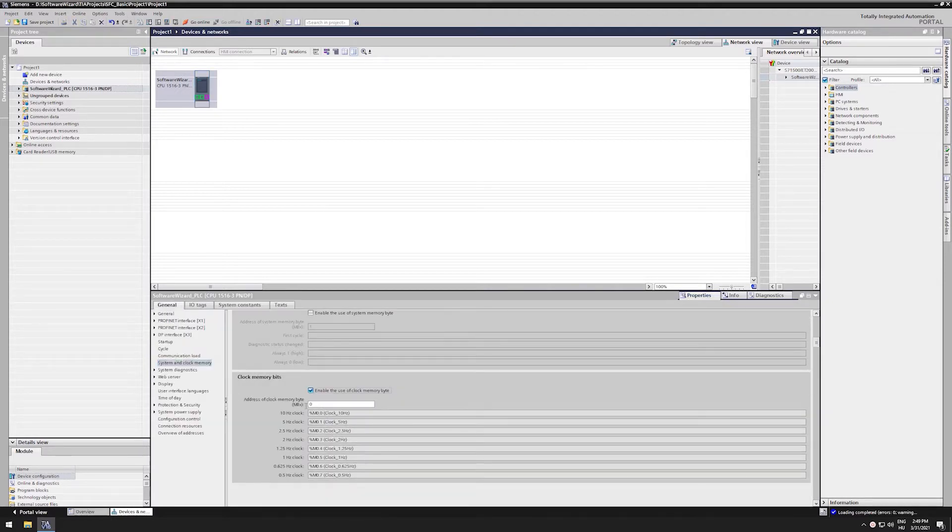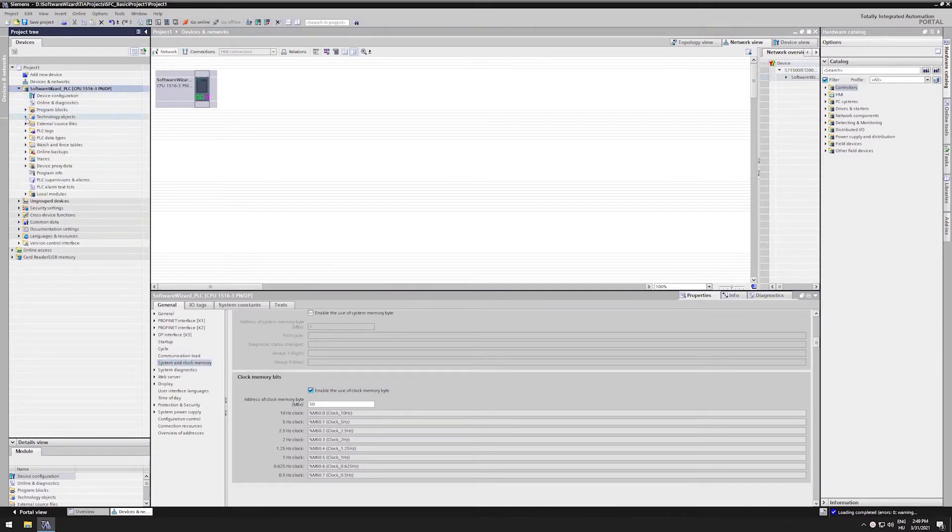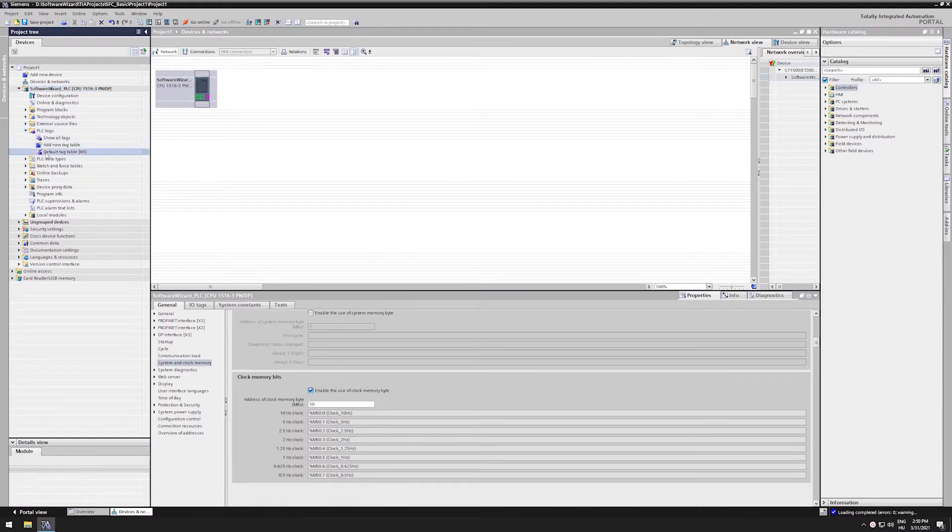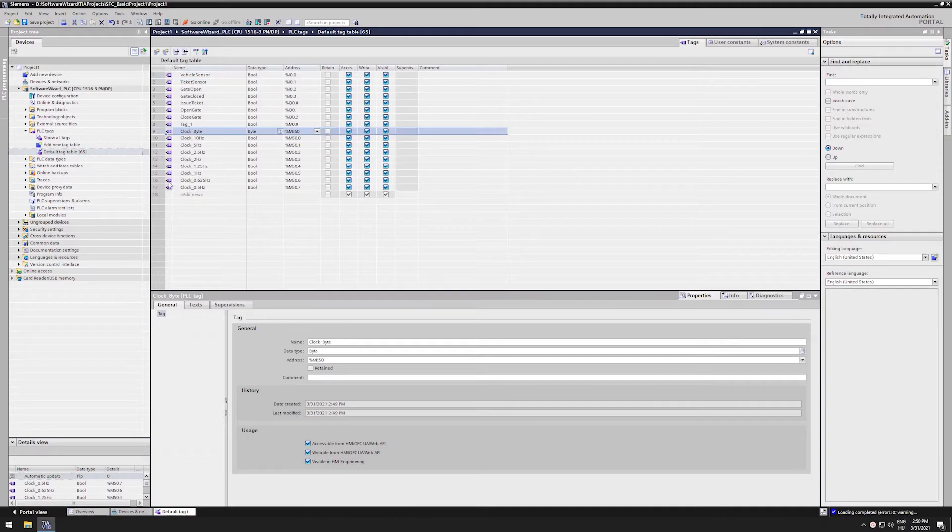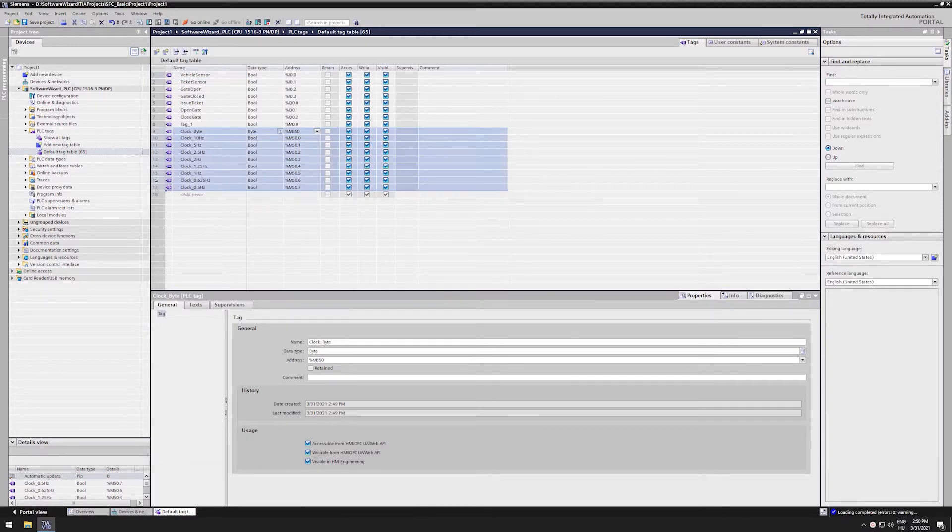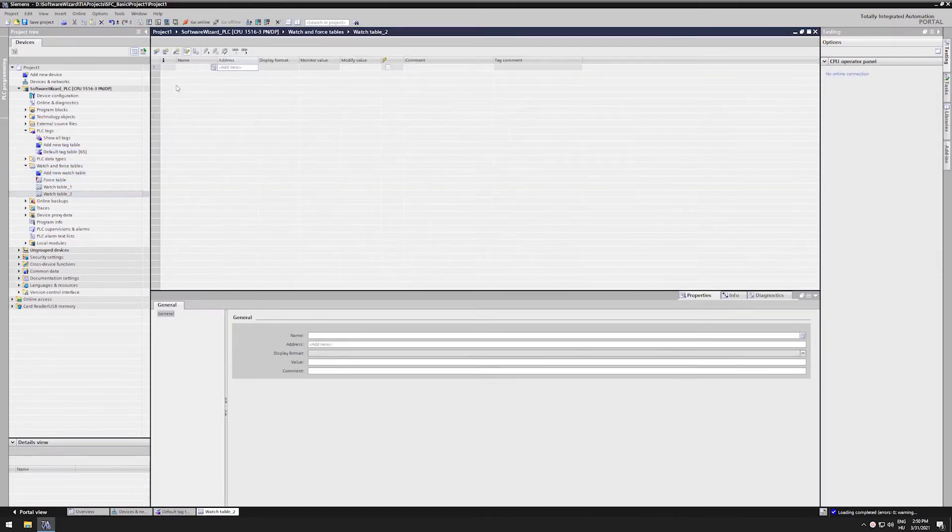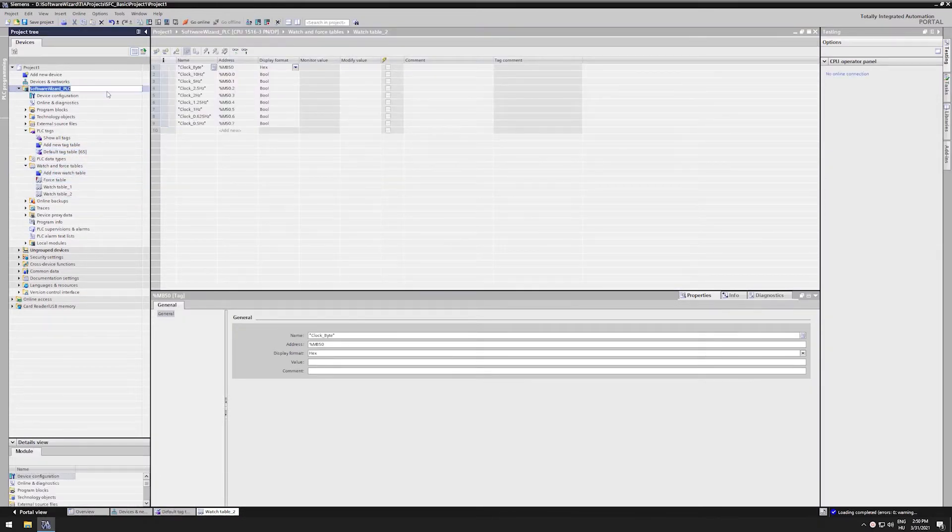I will use byte 50, it does not matter which address we are using, but be careful, these bits will also remain writable from the user program. And writing memory byte 50 can lead to some malfunctions in your program. TIA Portal automatically generates the tags for us and names our bits with the corresponding hertz value. Let's download the new configuration first and copy these tags and check if they work from a watch table.